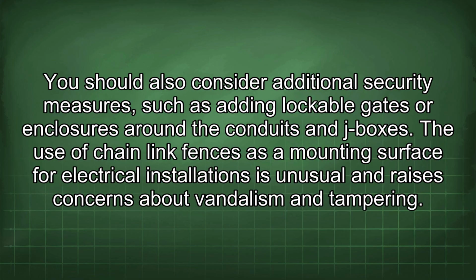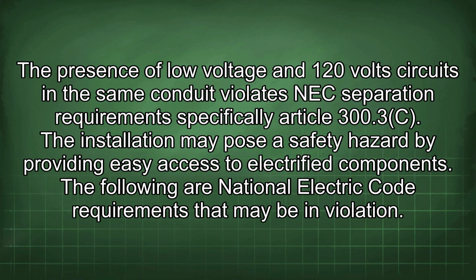You should also consider additional security measures, such as adding lockable gates or enclosures around the conduits and J-boxes. The use of chain link fences as a mounting surface for electrical installations is unusual and raises concerns about vandalism and tampering. The presence of low voltage and 120 volt circuits in the same conduit violates the NEC separation requirement, specifically Article 300.3c. The installation may pose a safety hazard by providing easy access to electrified components.